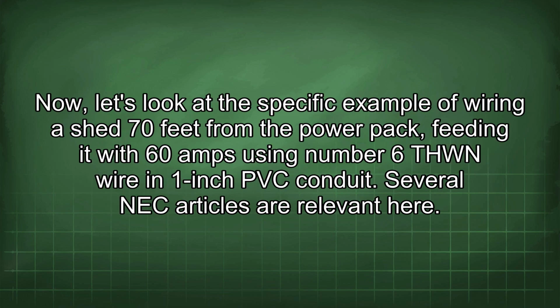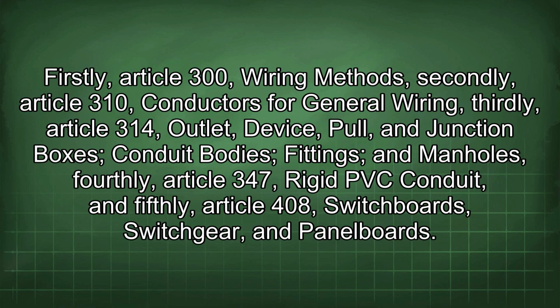Now let's look at the specific example of wiring a shed 70 feet from the power pack, feeding it with 60 amps using number 6 THWN wire in 1-inch PVC conduit. Several NEC articles are relevant here. Firstly, Article 300, wiring methods. Secondly, Article 310, conductors for general wiring. Thirdly, Article 314, outlet, device, pull, and junction boxes, conduit bodies, fittings, and manholes. Fourthly, Article 347, rigid PVC conduit. And fifthly, Article 408, switchboards, switchgear, and panel boards.